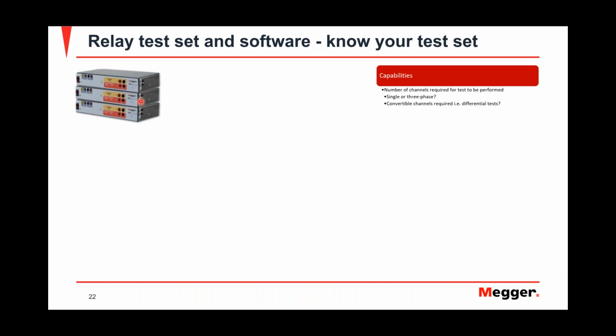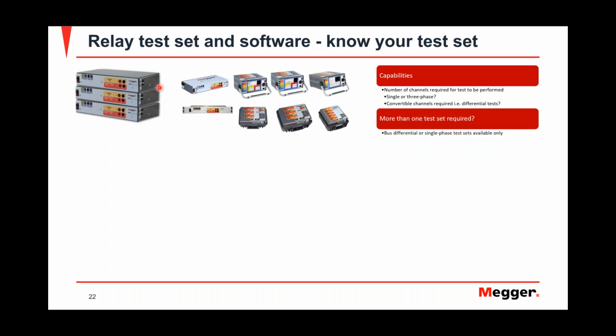But if you're testing an electromechanical relay that's only single phase, then you only need 1 single phase unit, and you don't have to bring the big heavy test set. So know the capabilities and the equipment that you have. Let's say you're testing bus differential, and you have a low impedance bus differential relay, and you want to test different scenarios that require more current channels than 1 test set could provide. Knowing that you could daisy chain them and that you're going to require 2 test sets to get 12 currents, keeping that in mind will help you.